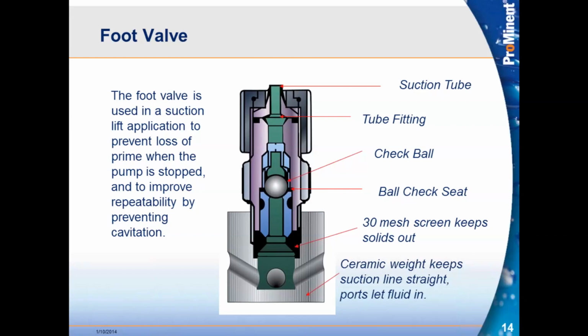Below that check, we do have a mesh screen to keep solids out. So if you do have a chemical that may have contamination in it from time to time, you will have to clean out that mesh screen, so keep that in mind. The other thing you see at the bottom is a ceramic weight. So this foot valve, not only does it help us keep the pump primed, but it also helps keep that tubing nice and vertical down in our supply tank with that weight. If the chemical that we're pumping is, for example, fluoride, we know that fluoride isn't compatible with ceramic.